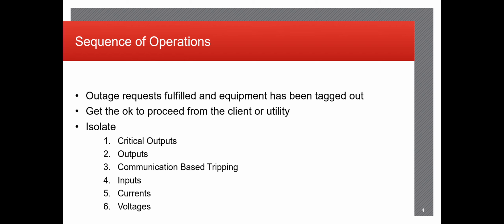Once you get the okay from the client or utility to proceed, this is how you go step by step to isolate a relay. So the first thing you want to take out is any of the critical outputs that may be in the circuit that you're isolating. This is done first specifically because a relay looks at the voltage and currents flowing in and out of it. If you disrupt any of those voltage or currents, the relay believes that there's an issue and it's going to send an operating signal to any of the breakers that are in that scheme.